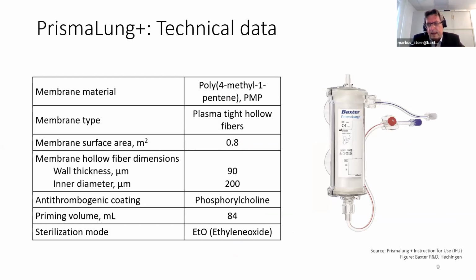So we have implemented these design principles in the PRISMALUNG Plus device. As a membrane, we use hydrophobic hollow fiber PMP, polymethylpentene, which has a thin, dense outer layer to prevent plasma breakthrough. Despite this very dense layer, PMP membranes are highly efficient in CO2 transport due to the high intrinsic gas permeability of PMP. The membrane surface area in PRISMALUNG Plus is 0.8 square meter. And to prevent protein binding to the membrane via hydrophobic interaction, which could initiate blood coagulation pathways or inflammatory pathways, the PMP membrane in PRISMALUNG Plus is coated with phosphorylcholine. This is a zwitterionic phospholipid.